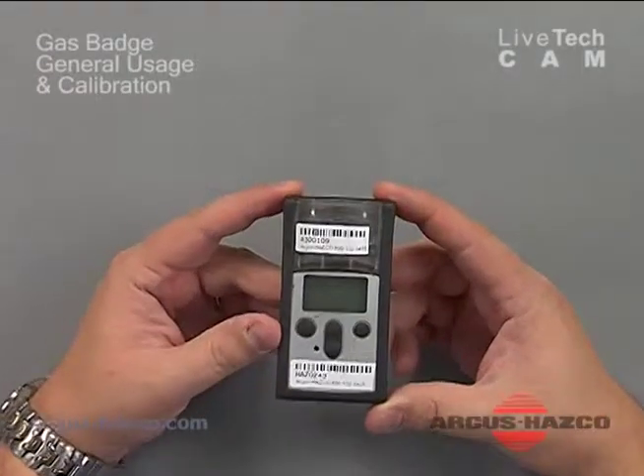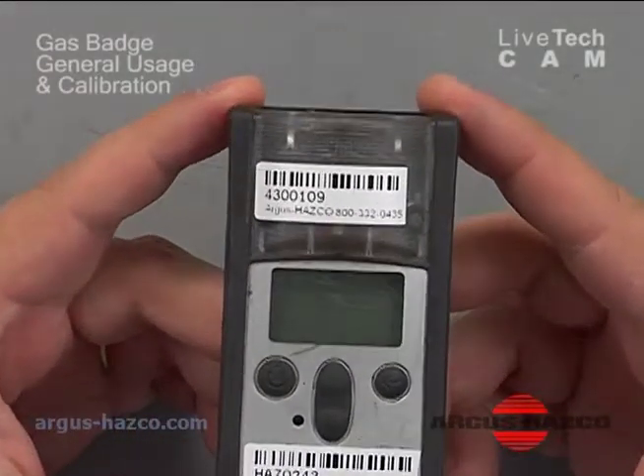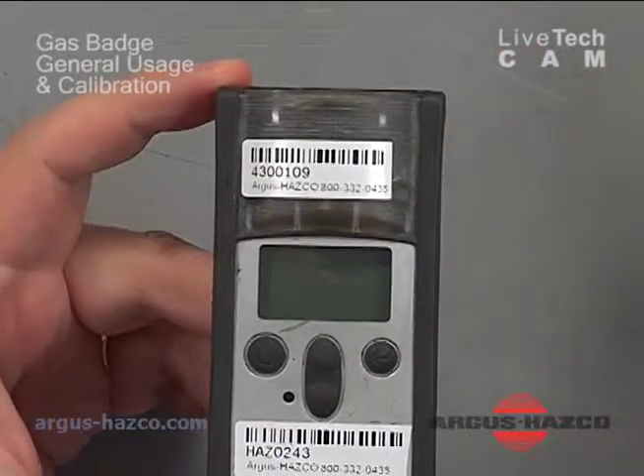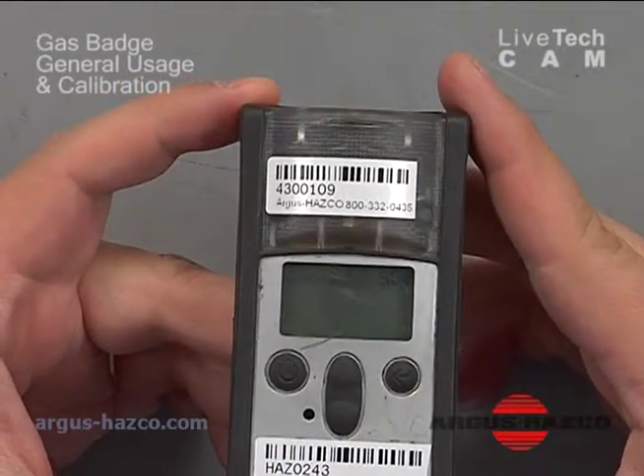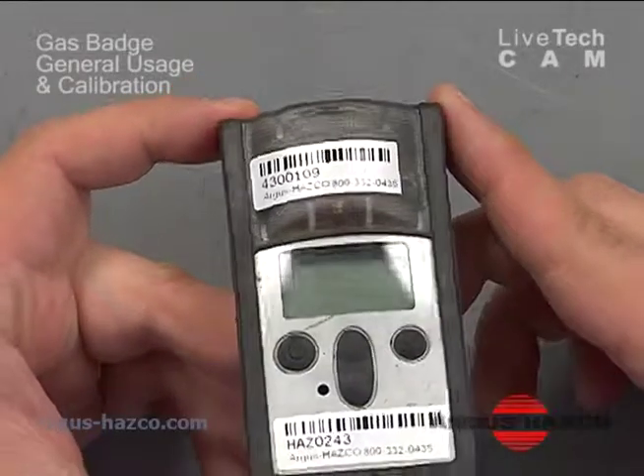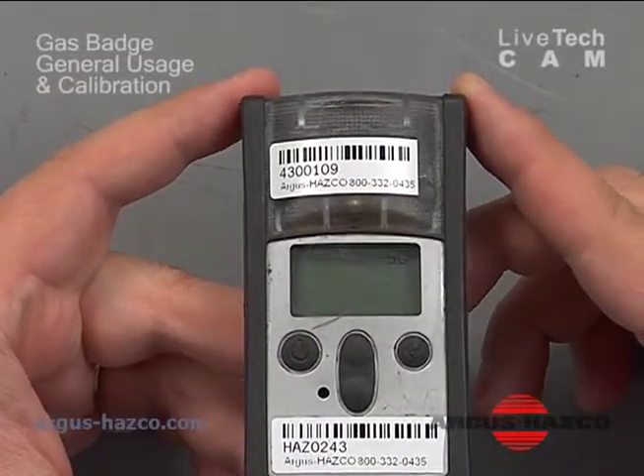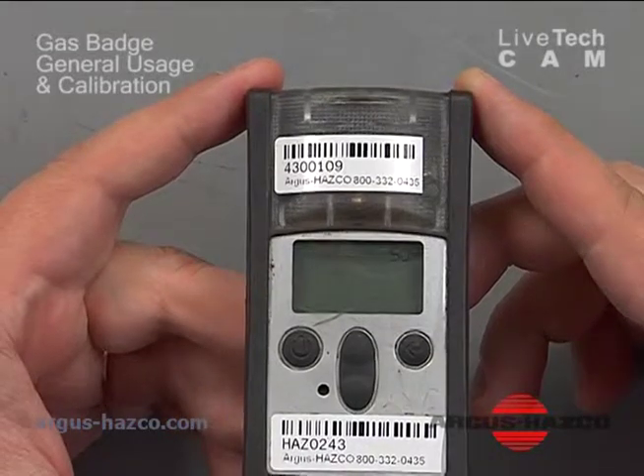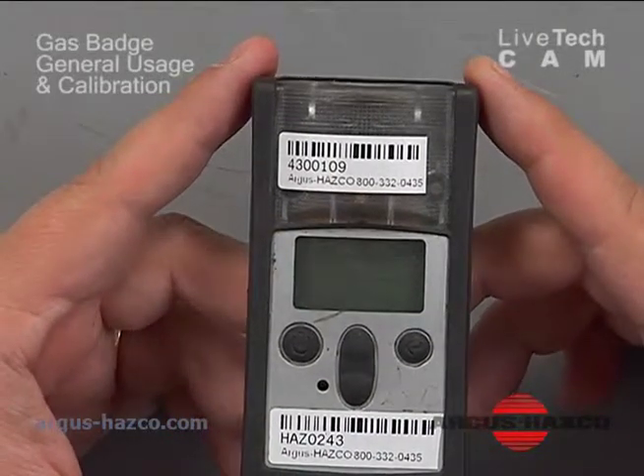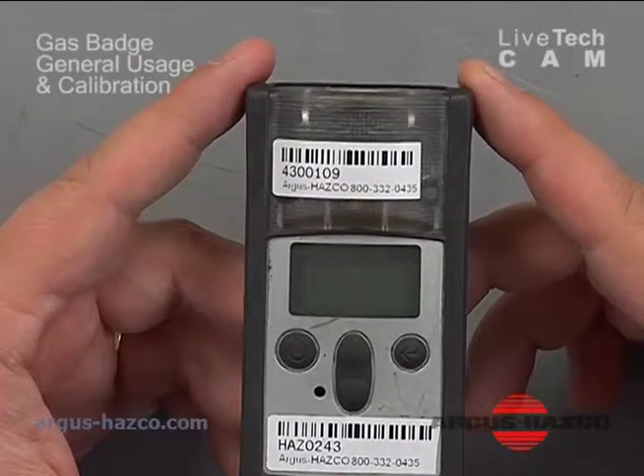Hello, today we're going to discuss the Industrial Scientific Gas Badge Pro and the calibration of a Gas Badge Pro. Right here you have your Industrial Scientific Gas Badge Pro, and it's a single gas monitor. You can put multiple sensors in this instrument to detect a variety of different types of single gas sensors they have for this. Up in the top right, you can tell this one is configured for SO2, sulfur dioxide. So in order to calibrate this, you're going to need a cylinder of sulfur dioxide as your target gas.